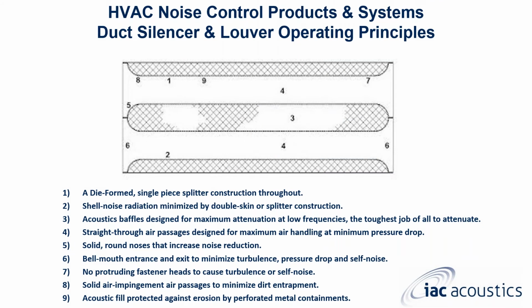Now, this is a little bit different picture than what you just saw. This one here is IAC's famous bell mouth entrance and exit type silencer. 99% of our silencers are going to have this look on both sides. So the left side versus the right side, it's the same. This here minimizes turbulence, pressure drop, and self noise. The straight air through passages are designed for maximum air handling, again with minimum pressure drop. Acoustic baffles with this type of design are for maximum attenuation at low frequencies, which is roughly the toughest job to attenuate.